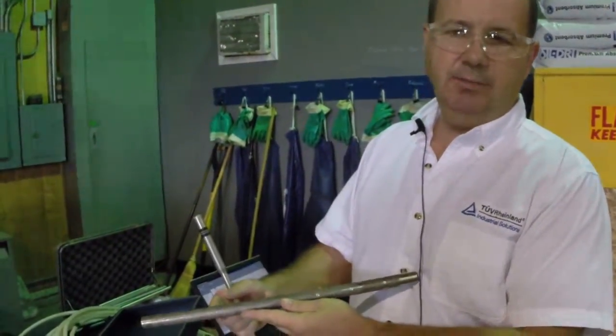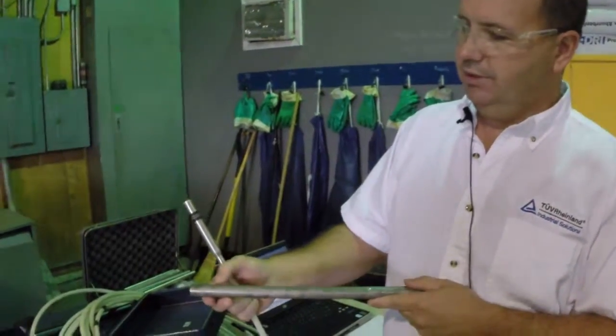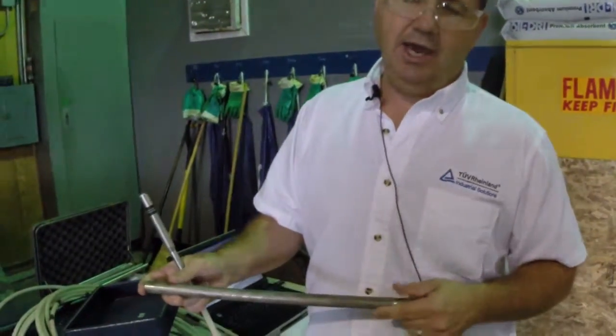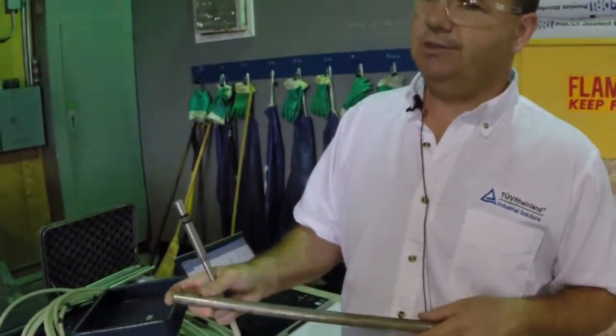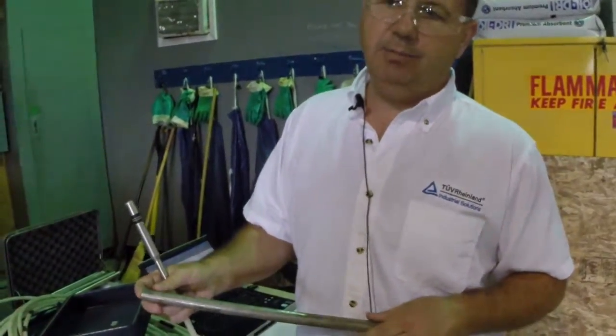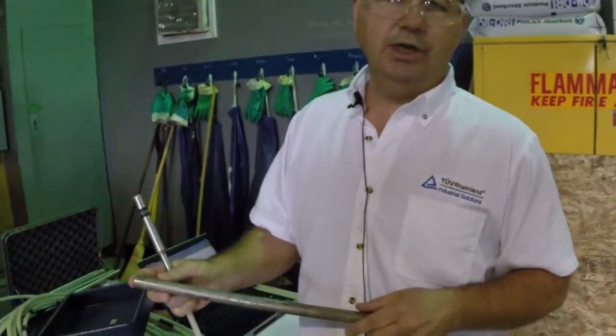We have a known calibration standard, so we can set up our equipment. This calibration standard has an ID notch. It has a 100% through wall hole, 80%, 60, 40, and a 20% OD groove. This is an ASME calibration standard. It's the way we set up our equipment, so when we're running into defects or hitting indications, we can calibrate and get an accurate sizing for that defect.